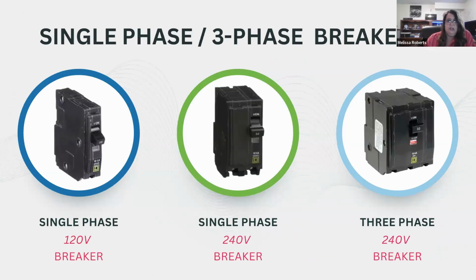These are just some pictures of what breakers look like in their different configurations. If you're looking at a space and you look in the panel and notice it's filled with single phase 120 volt breakers, more than likely you've got single phase power coming in. On the other side, if you look in the panel and notice three-phase breakers taking up three spaces, then you have three-phase power. You can run single phase off of three-phase, but not three-phase off of single phase. And the little one in the middle is a single phase 240 volt breaker — like at your house, if you have an electric dryer, it's running on one of these bigger breakers.